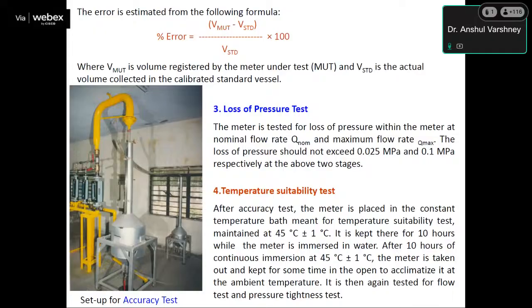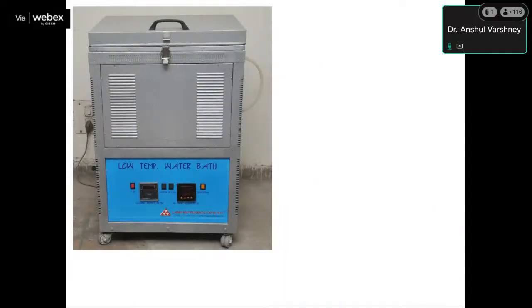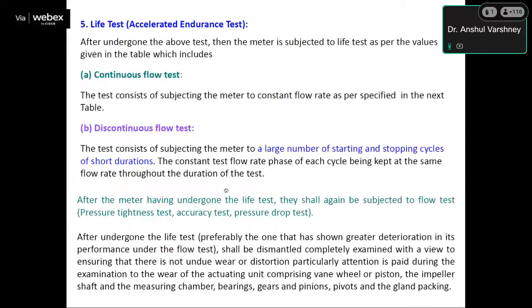Temperature suitability test. After the accuracy test, the meter is placed in the constant temperature bath meant for the temperature suitability test, maintained at 45 degrees centigrade plus minus 1 degree centigrade. It is kept there for 10 hours while the meter is immersed in water. After 10 hours of continuous immersion at 45 plus minus 1 degrees, the meter is taken out and kept for some time in the open to acclimatize it to ambient temperature. It is then again tested for the flow test and pressure tightness test. So this is a low temperature water bath system.